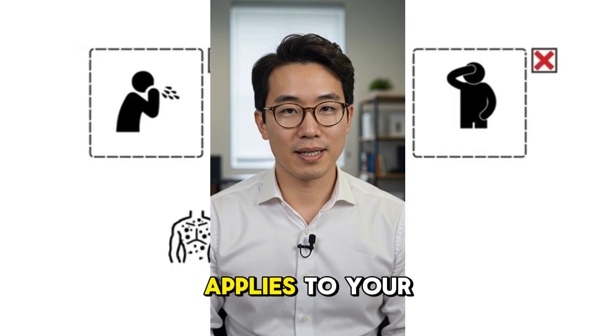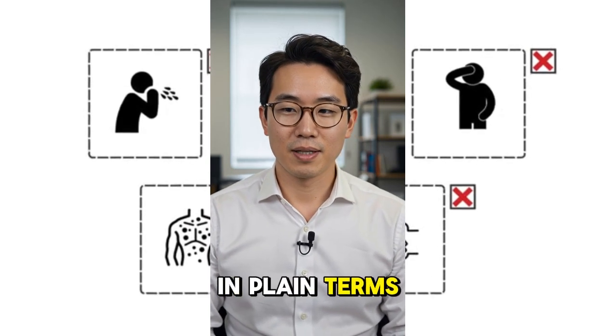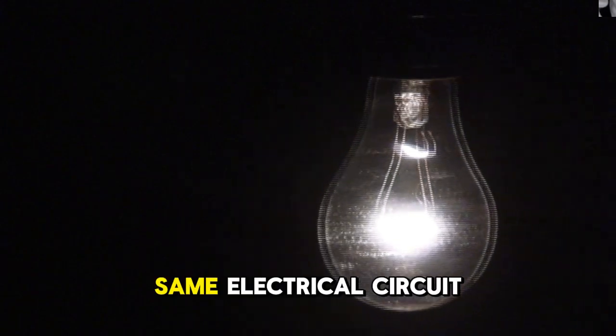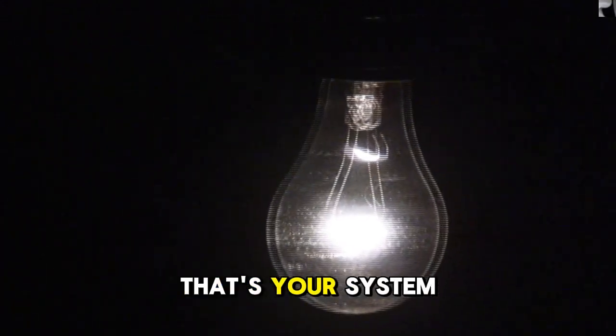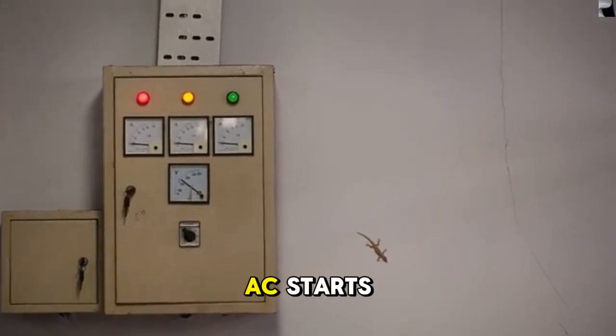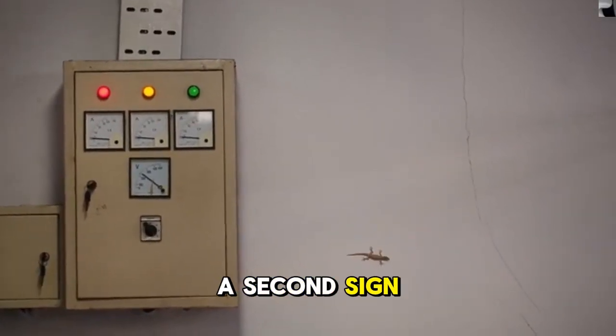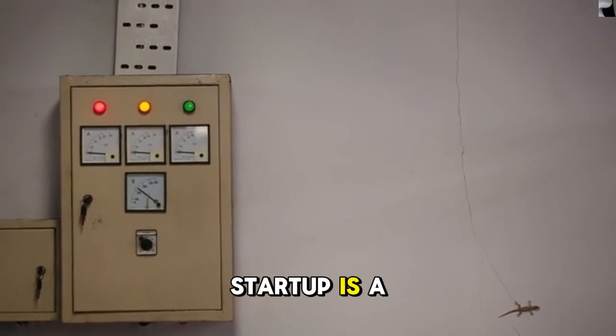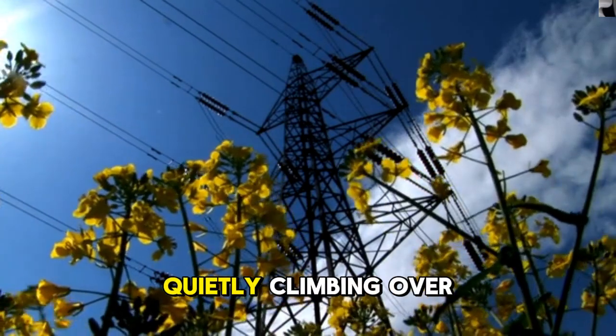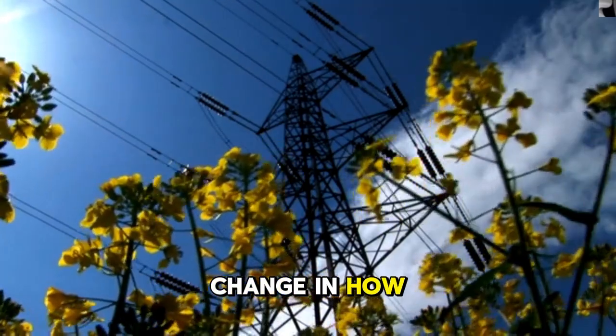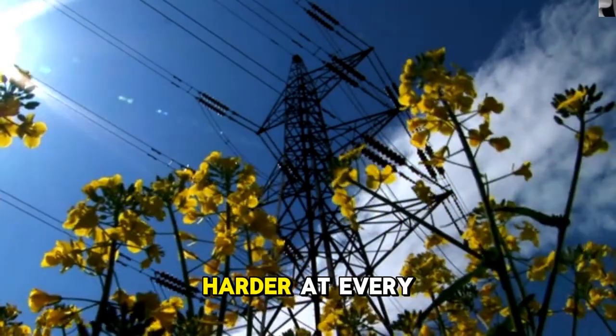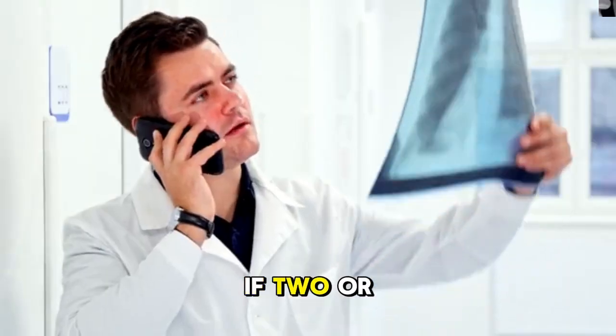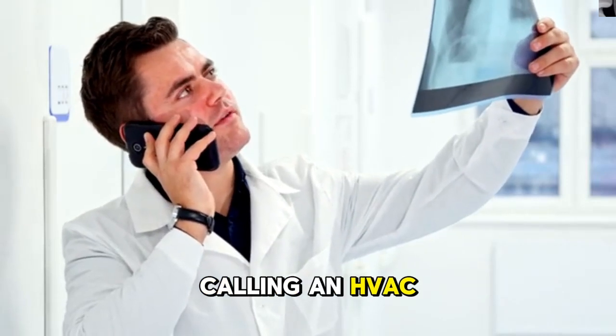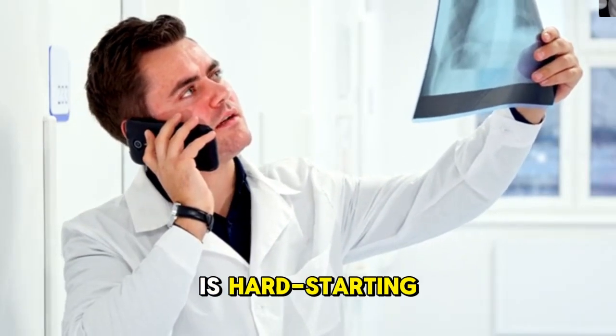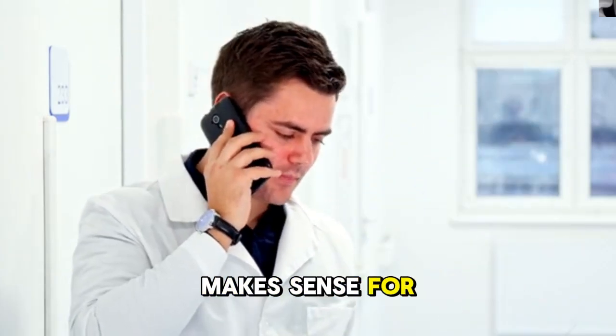If you want to know whether this applies to your system, here's how to check it yourself, in plain terms. Watch a light in the same room or on the same electrical circuit as your outdoor unit. If it visibly dims the moment the AC kicks on, that's your system telling you something. If your breaker has tripped when the AC starts even once, that's a second sign. A clicking or stuttering sound right at startup is a third. And if your electricity bill has been quietly climbing over the past few summers with no real change in how you use the AC, an aging compressor working harder at every startup could be part of the story. If 2 or more of these sound familiar, it's worth calling an HVAC technician and asking directly whether your system is hard starting and whether a hard start kit makes sense for your unit specifically.